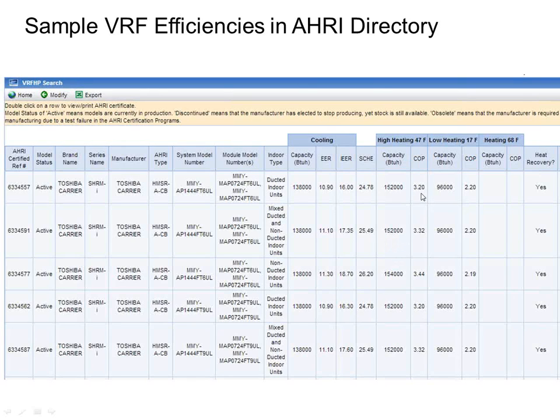My COP at 47 degrees, which is indicated up on the top of the screen there. At 47 degrees, he's a 3.2 COP, or if you want to think of it this way, 320% efficient. My 17 degree number, he dropped down to only 220% efficient. And if I had one that was a minus 5 or 0 degree COP number, he'd probably be like 1.4 or 1.5 or something like that if they rated it that way. Clear that off the screen for you too. And then on the very last column is heat recovery, yes or no. In this case, they're all heat recovery units.